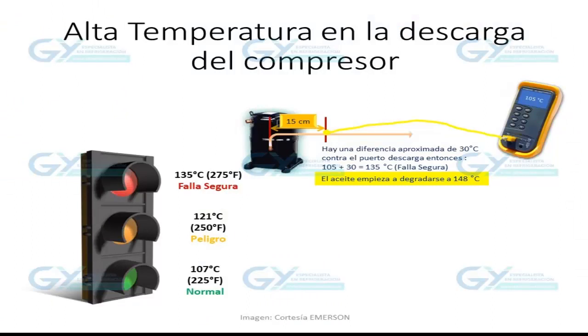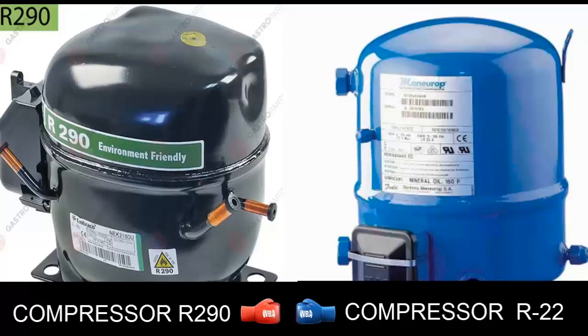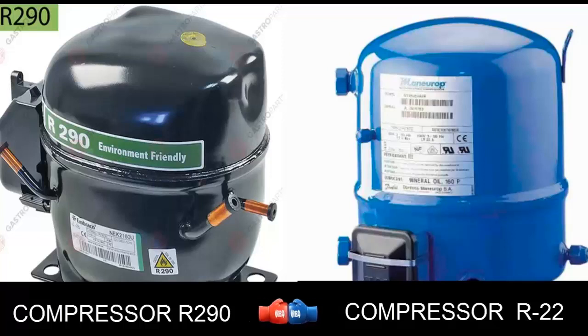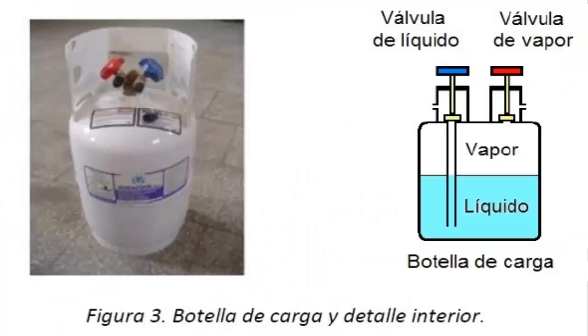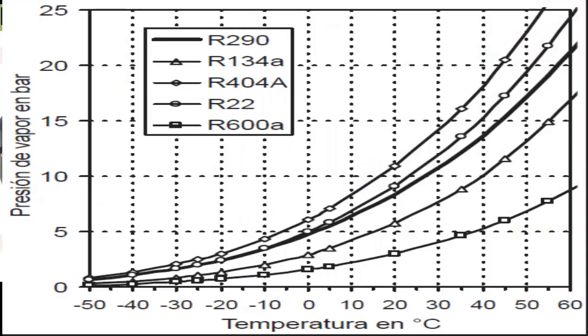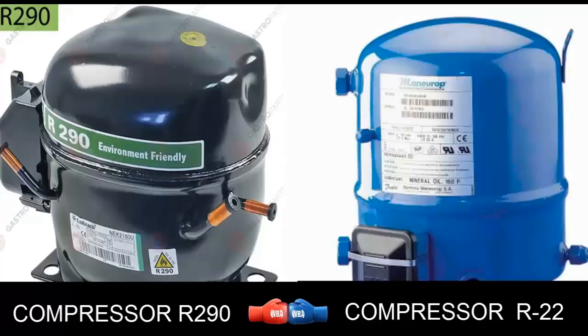The temperature at the compressor outlet is significantly lower when R290 is used compared to the resulting temperature when using R22. Both the compressor with R290 and the compressor with R22 can be charged in liquid phase as well as vapor without a problem. The pressures of R290 and R22 are not identical, but they are quite similar.